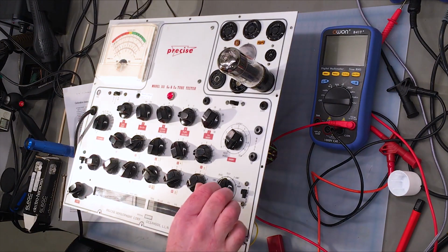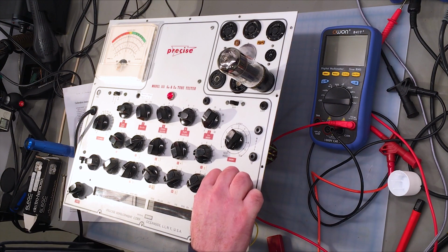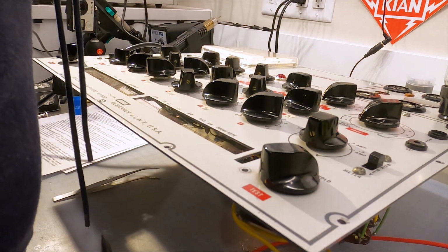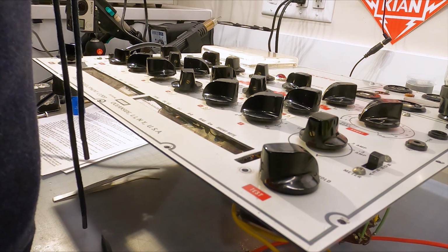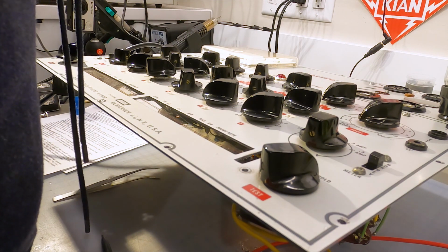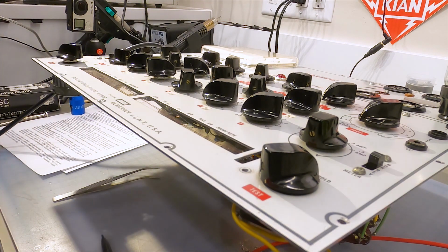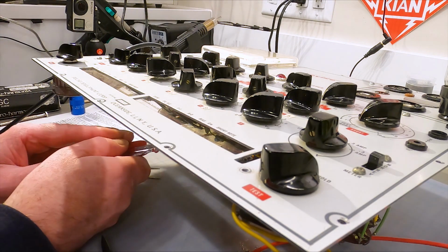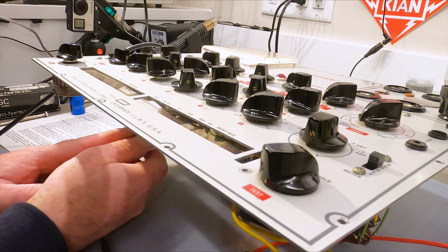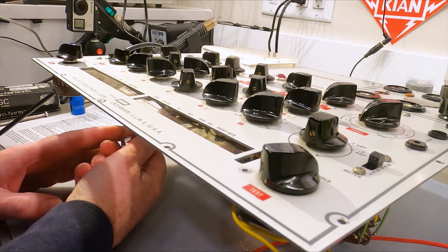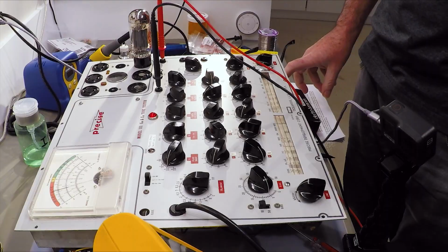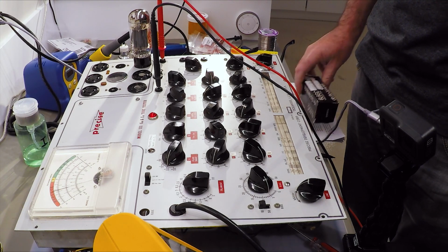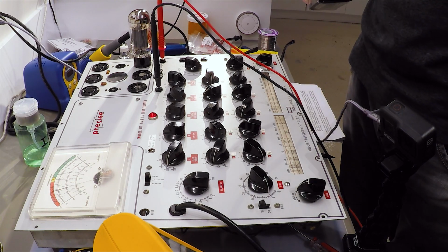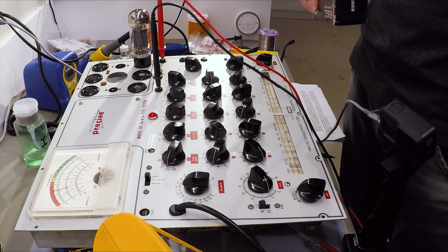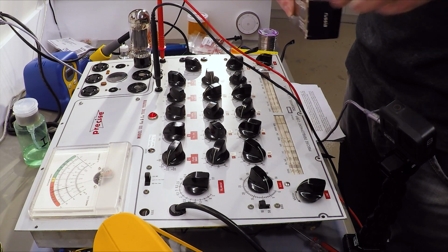And 30, go back, check the line, it's still the same, bias, still the same, and test, it's giving me, well, it's reading a little, oh no, it's giving me just a little bit more than I should be getting. So I'll just adjust this slightly with P8. P8. Done. Well, we have tried somewhat unsuccessfully to calibrate the emission readings on this precise model 111 tube tester.